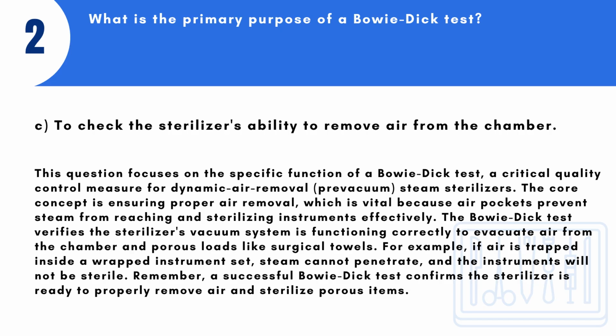The Bowie-Dick test verifies the sterilizer's vacuum system is functioning correctly to evacuate air from the chamber and porous loads like surgical towels. For example, if air is trapped inside a wrapped instrument set, steam cannot penetrate, and the instruments will not be sterile. Remember, a successful Bowie-Dick test confirms the sterilizer is ready to properly remove air and sterilize porous items.